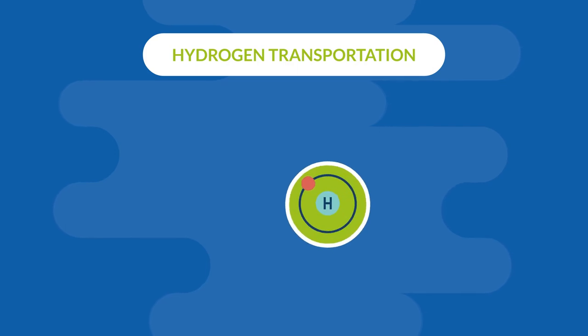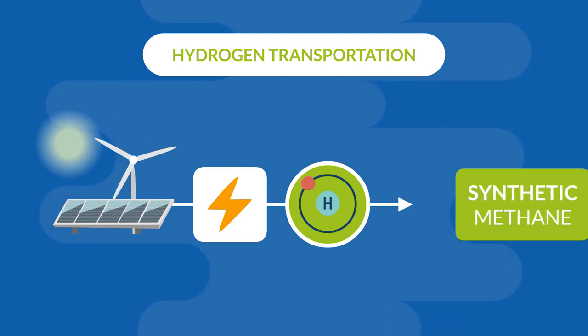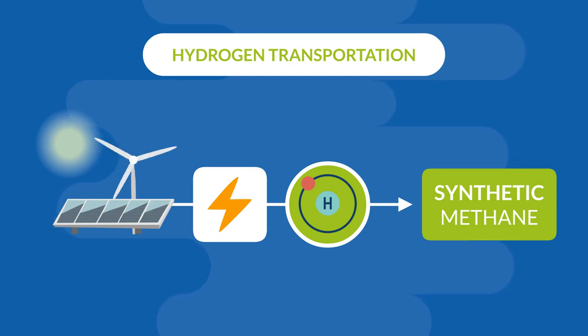Hydrogen transportation: Hydrogen can be transported in the form of a gaseous energy carrier via the natural gas grid, such as power to gas. In this context, the German DVGW regulation states that hydrogen from electrolysis and synthetic methane must comply with a legal limit of up to 10% in the natural gas grid.